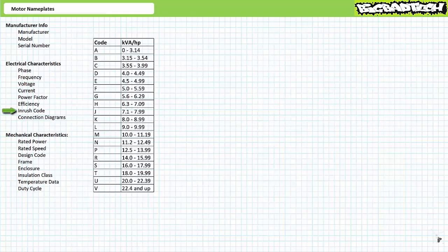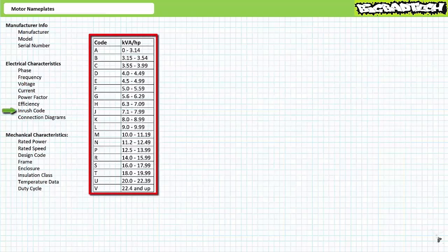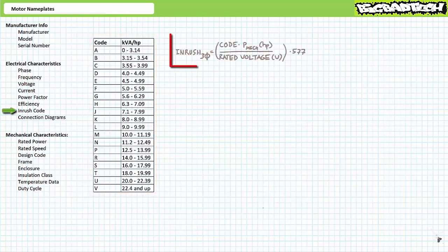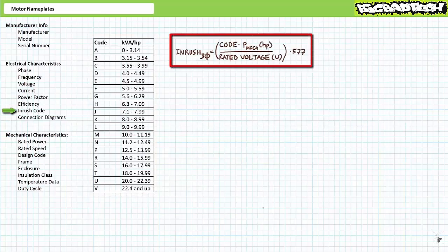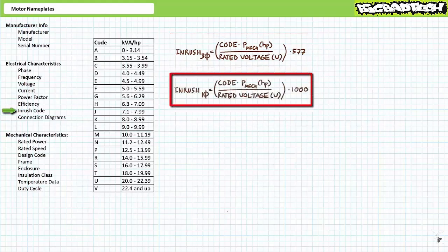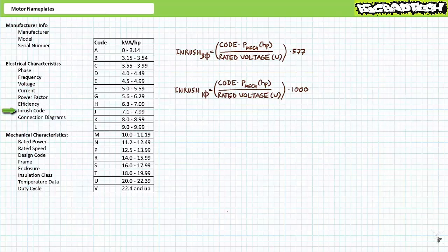Each letter in the inrush code refers to a range of constants in a kilovolt amperes per horsepower chart. You can estimate inrush current by using the constant in this calculation, where inrush for a three-phase AC motor is equal to the value of the code times the mechanical power in units of horsepower divided by the rated voltage times 577. If this is a single-phase AC motor, the 577 is replaced by the constant 1000. Notice there's no I, O, or Q code, and it stops at V. It's a trick question if the motor nameplate code features letters that don't appear on this chart.